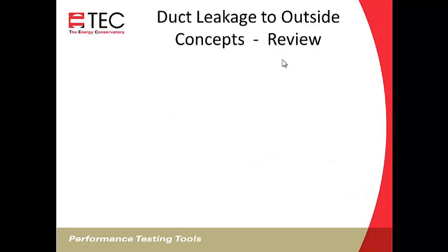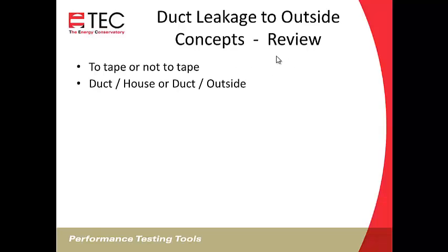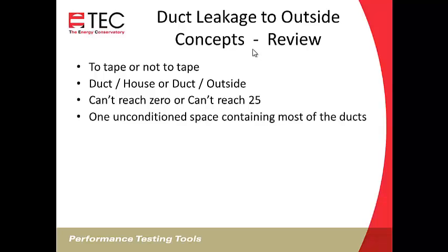So to review our duct leakage outside concepts, to tape or not to tape, it's our opinion you should always tape. Duct to house, duct outside, you can do the test either way, but we recommend measuring duct to house and cruising to zero. If you can't reach zero with the duct blaster fan, or you can't reach 25 with the blower door, then you need to drop that pressure down and use the can't reach pressure factors.